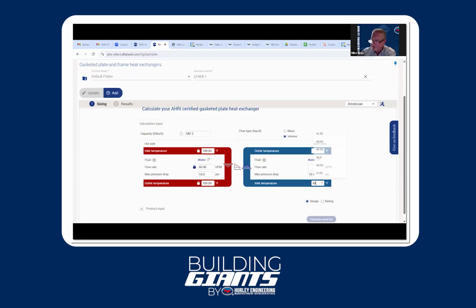Our inlet water temperature is 40, and our outlet side is 140. It will automatically calculate your gallons per minute requirement on that side. Notice, anytime we've locked something in, it shows a locked number, so you need to have at least one open value, whether it's outlet temperature or GPM, left blank so the system can calculate it.